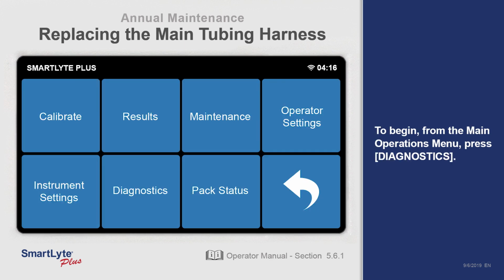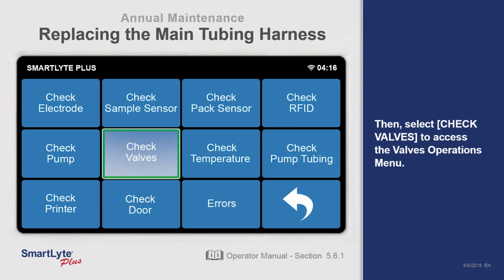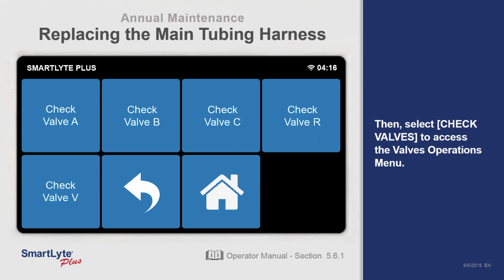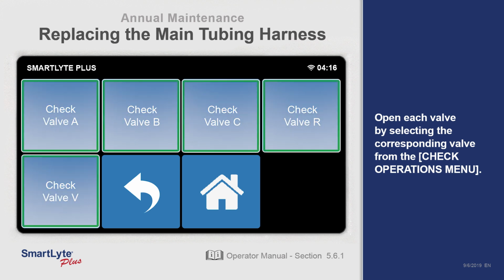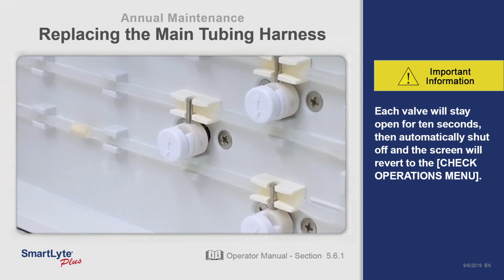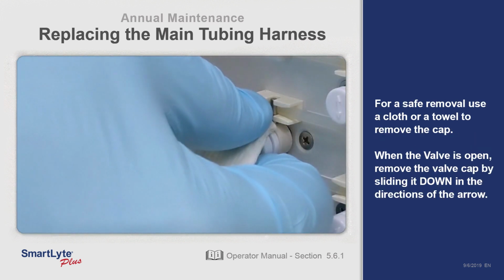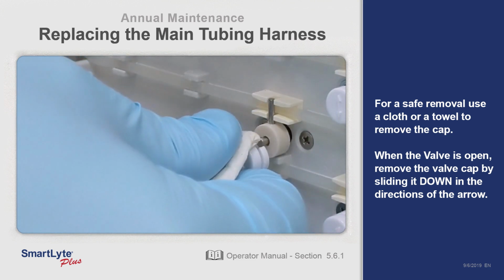To begin, from the main operations menu, press Diagnostics. Then select Check Valves to access the Valves Operations menu. Open each valve by selecting the corresponding valve from the Check Operations menu. Each valve will stay open for 10 seconds, then automatically shut off and the screen will revert to the Check Operations menu. For a safe removal, use a cloth or towel to remove the cap.